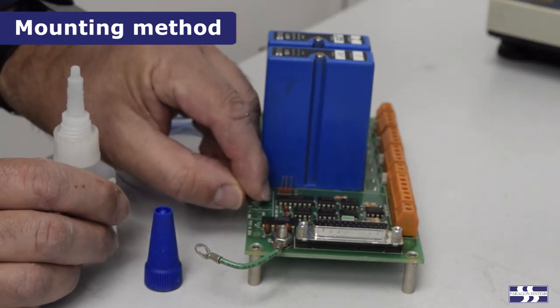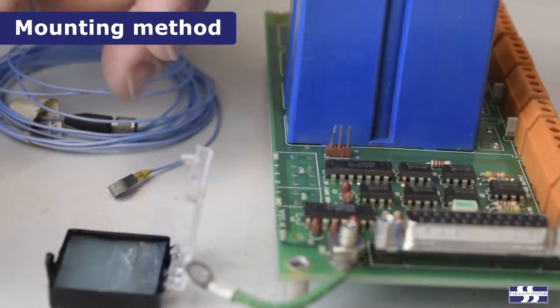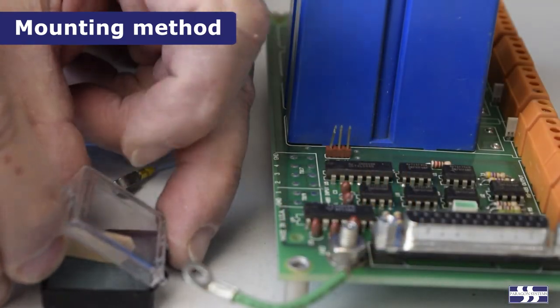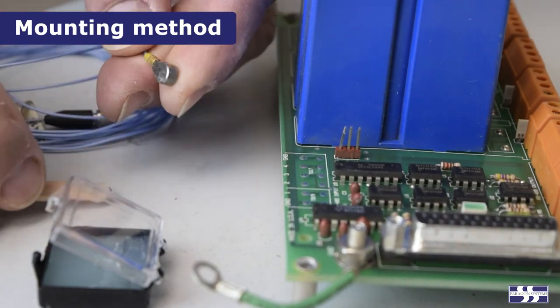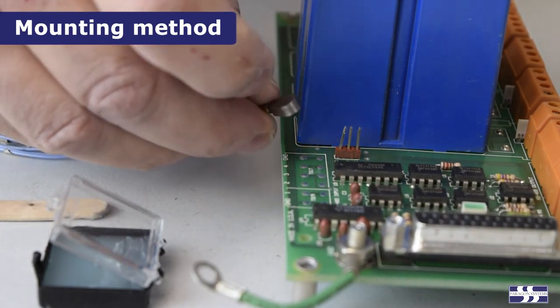For quick tests where the accelerometer needs to be moved around frequently, or for short duration tests, wax can also be used as an attachment method. However, this method can dampen the higher frequency response of the accelerometer.